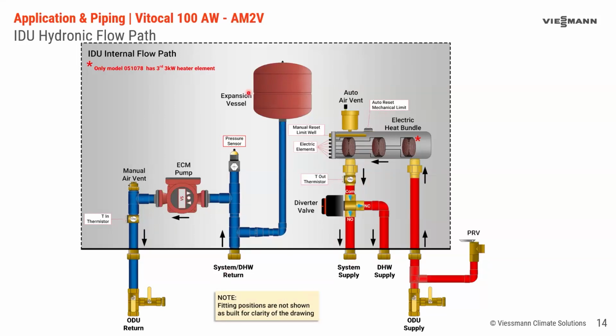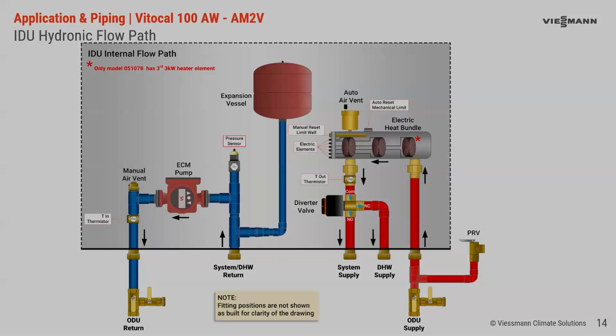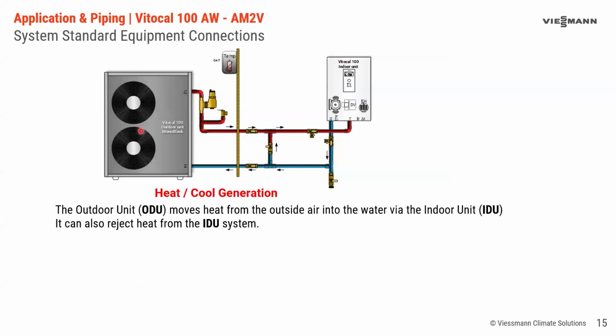So just as an internal function, the indoor unit is managing flow to the system, so either to the buffer tank or to the indirect tank, and it will also manage the set points and things like that. All your control logic for operating this heat pump is going to be in the indoor unit. Now, let's take this in little pieces here. So we're going to look at the part of the machine that is responsible for the energy.